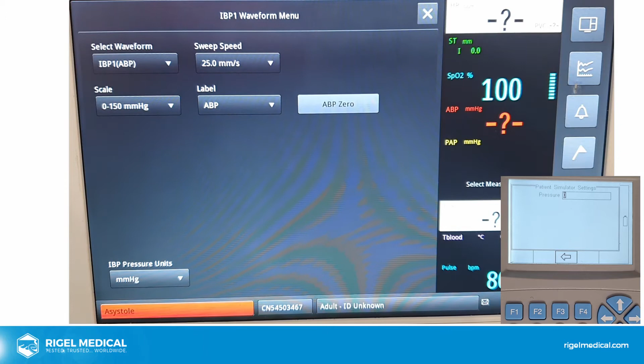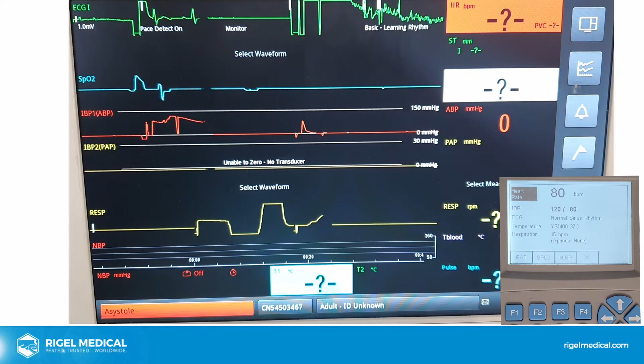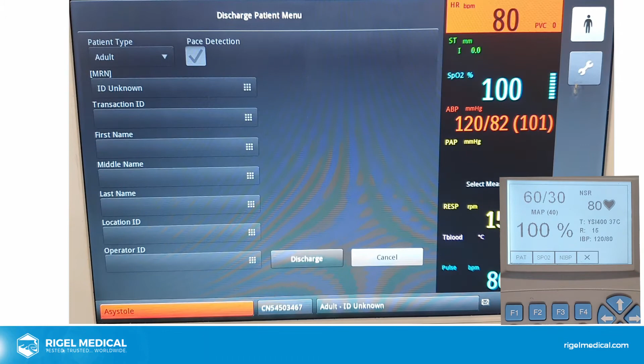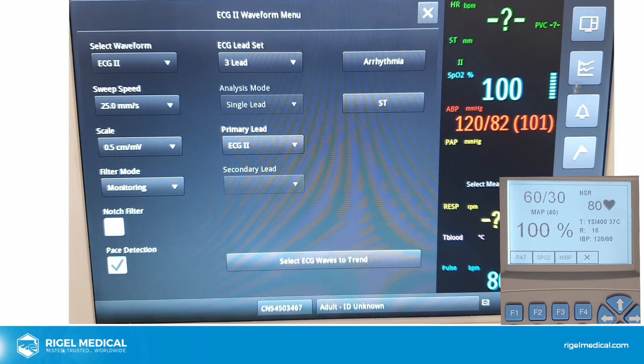We wait for the 0 to complete on the monitor. And we can come back out the PatSim menu, go home and start the manual simulation again. We need to select my number of ECG leads. And everything is as expected. The values are well within range. One more test we need to do, manual mode, is NIBP.